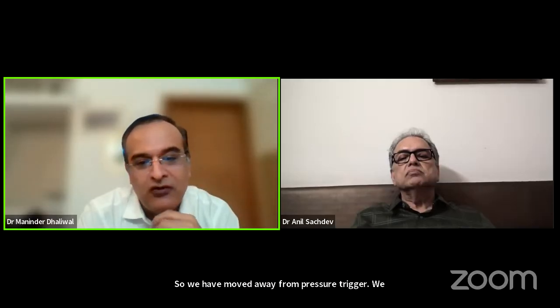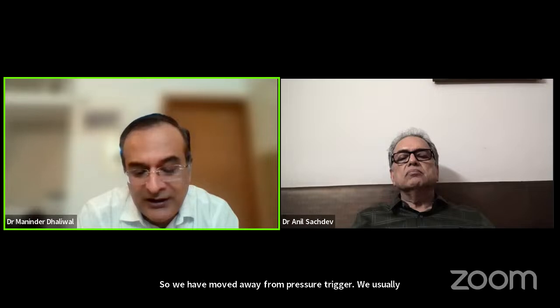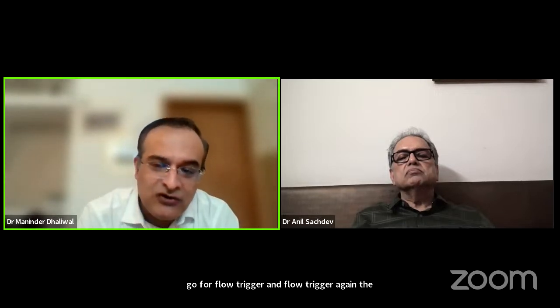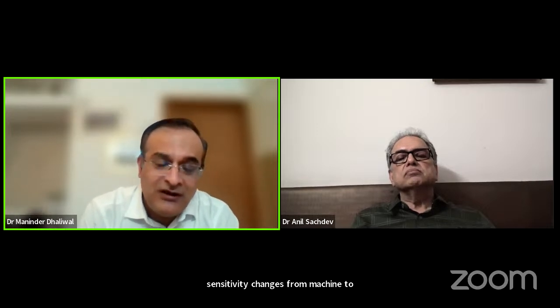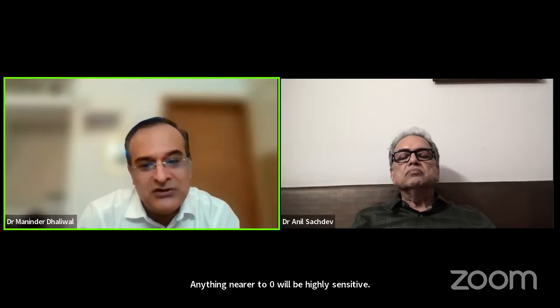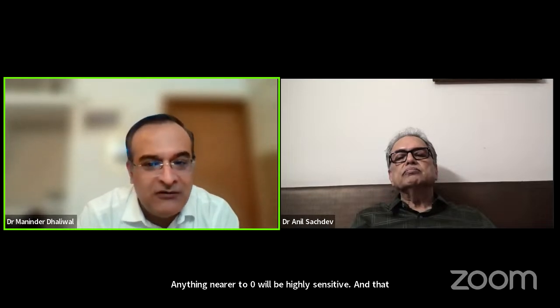We usually go for flow trigger. And in flow trigger, again, the sensitivity changes from machine to machine. Anything nearer to zero will be highly sensitive, and that means it's easy for a patient to take a breath, and away from zero would be difficult to take a breath.